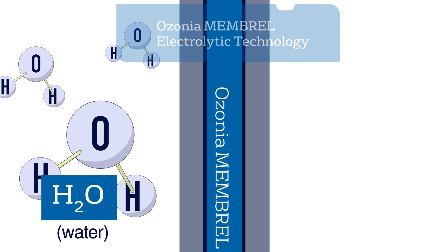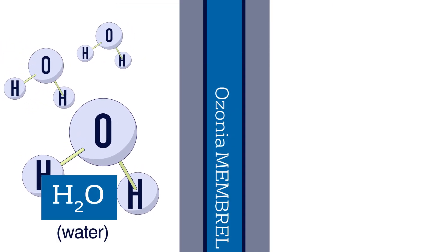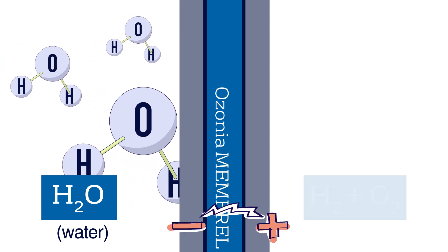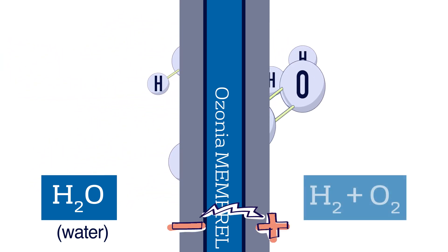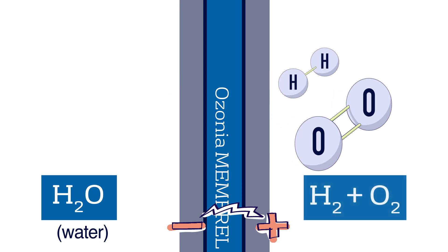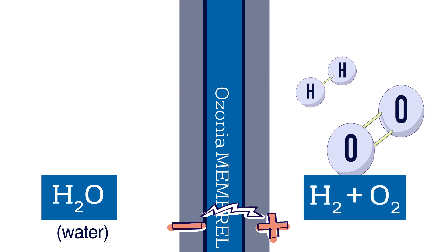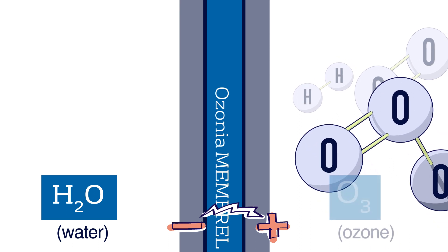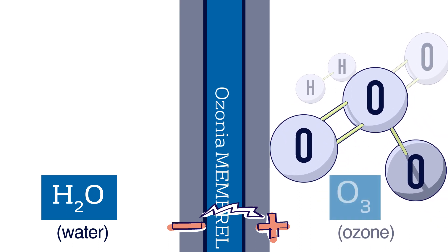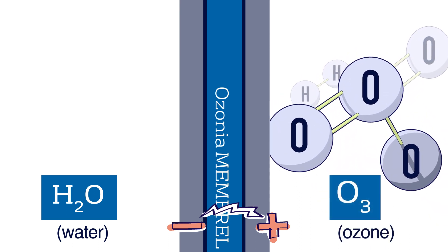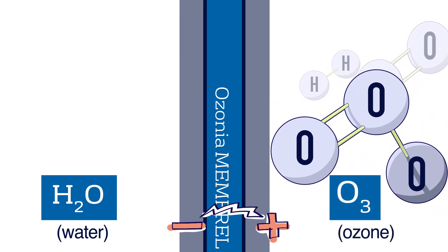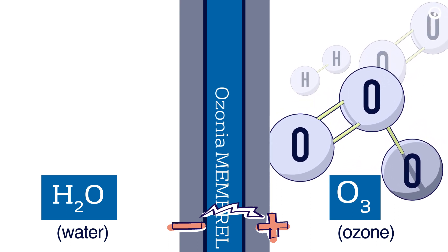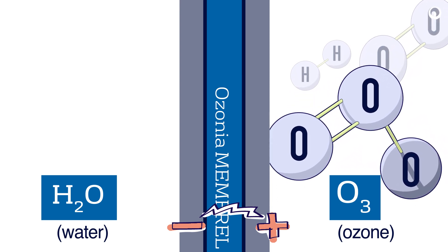Ozone is produced from ultrapure water via electrolysis. Water flows through the MEMBREL cell and is separated into oxygen and hydrogen. Oxygen is converted to ozone, a powerful oxidation agent. Because the only source component is the ultrapure water itself, no contaminants are introduced as with other technologies.